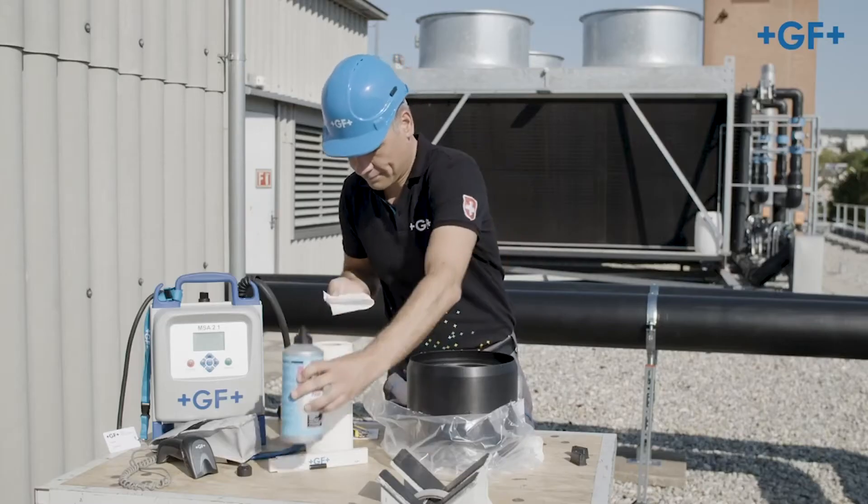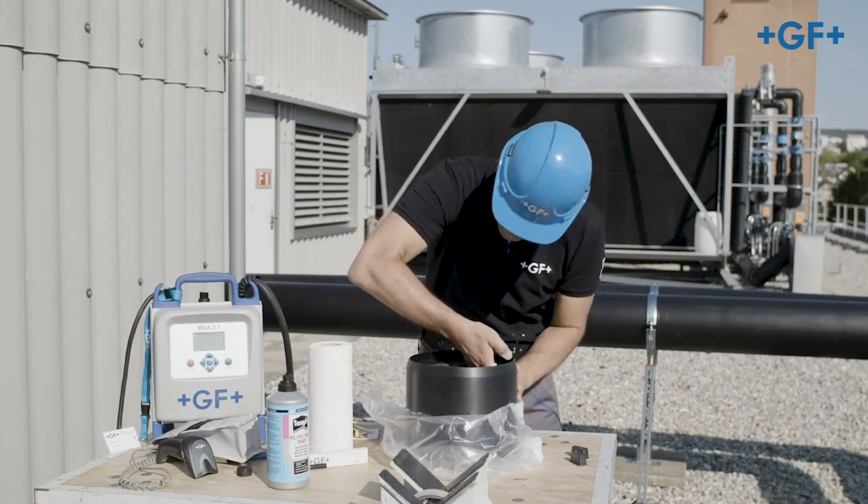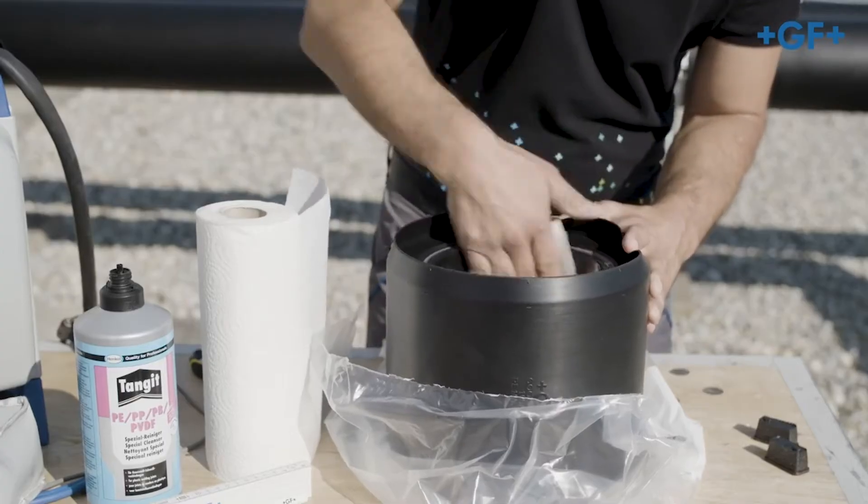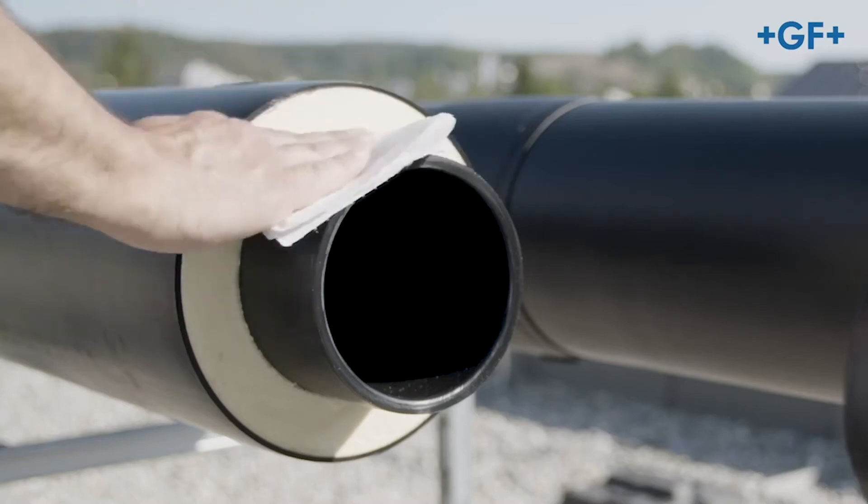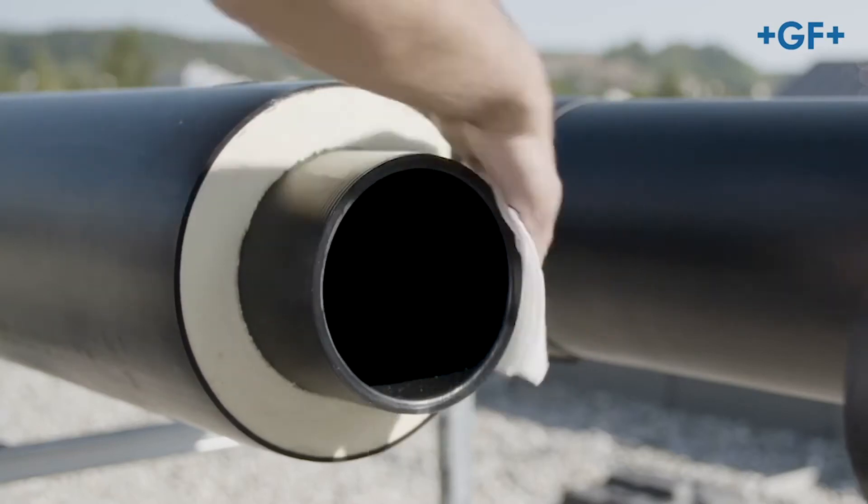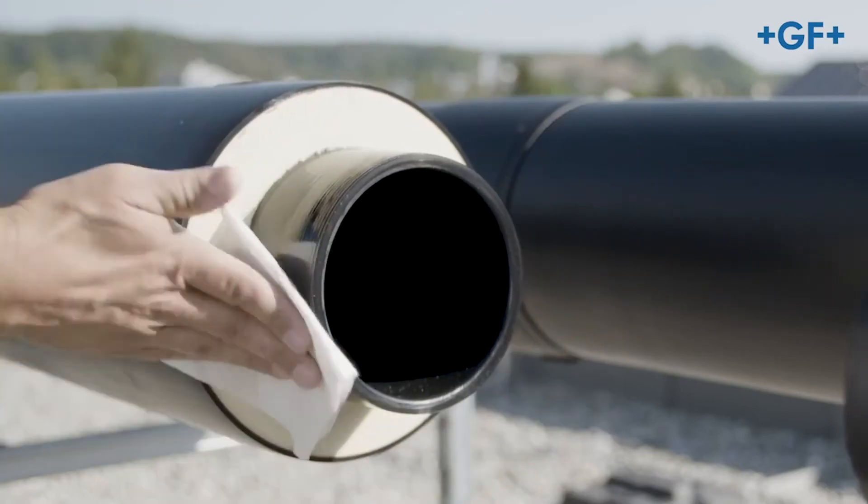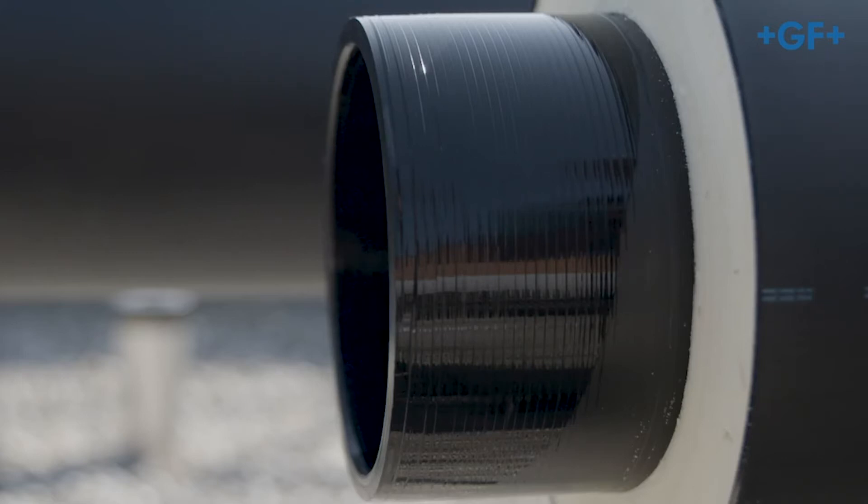Clean the welding surfaces of the CoolFit PE Plus fittings and pipes. For this purpose, use 90% or greater isopropyl alcohol and a clean, lint-free plain cloth. Wait until the cleaner has evaporated.